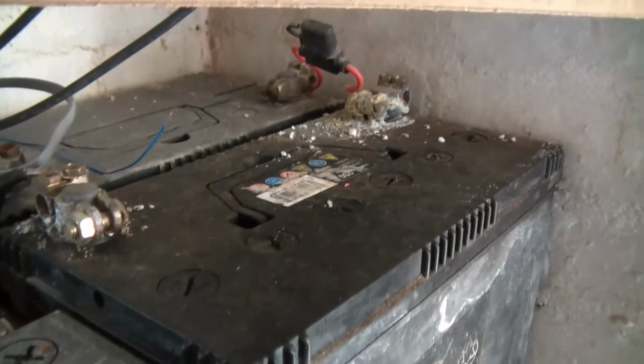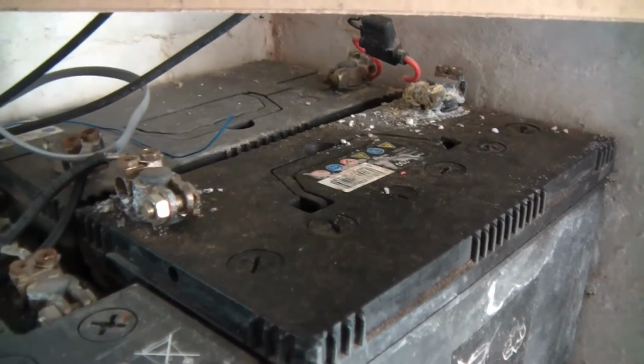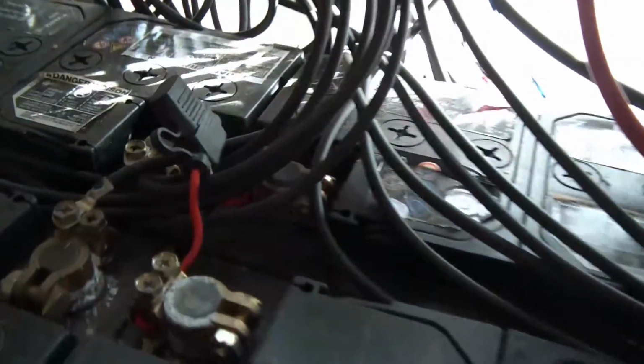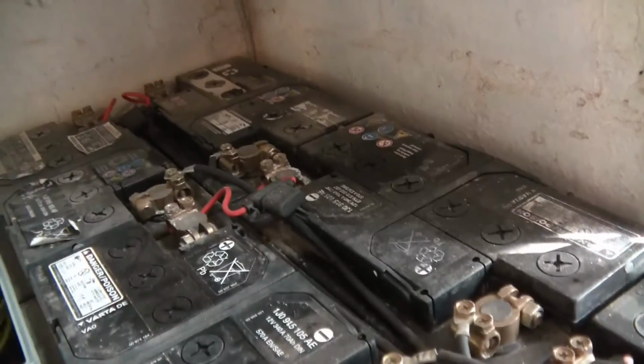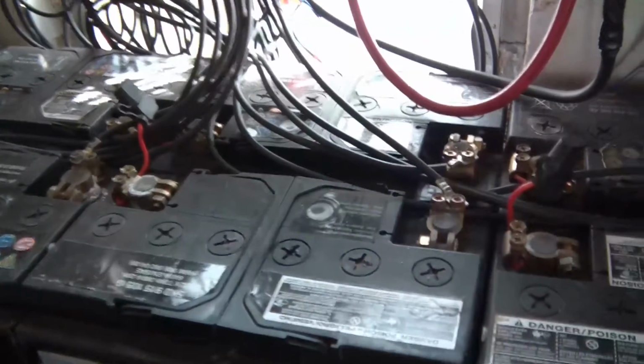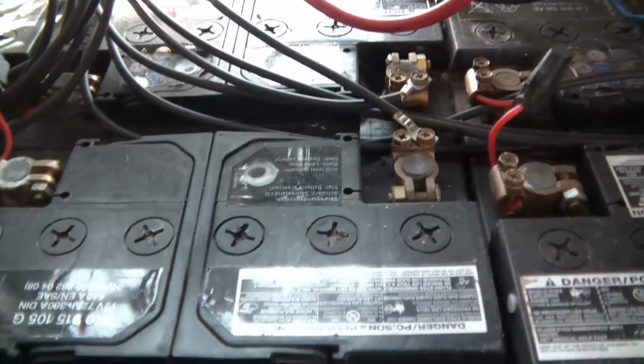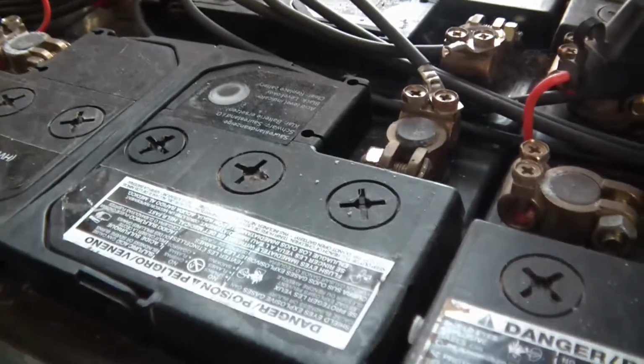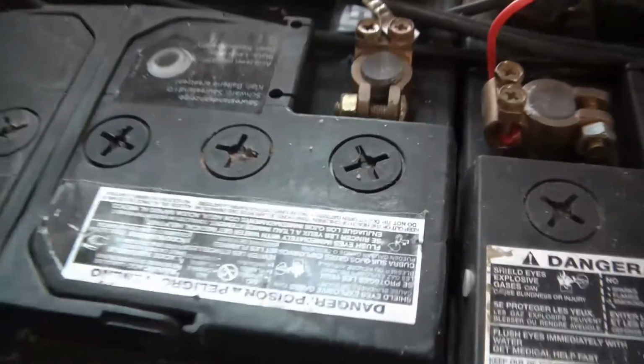First thing I noticed is there was some corrosion on one of the batteries, but not the rest. The rest looked fine. As you can see here, I've checked the fuses, and the fuses are all fine too. So there is another thing I need to check, and that is the water level. I'll just check this now.